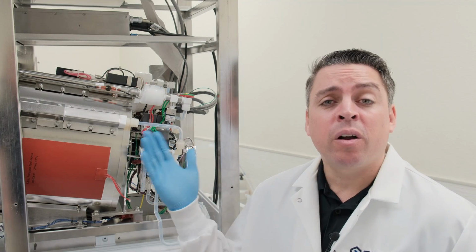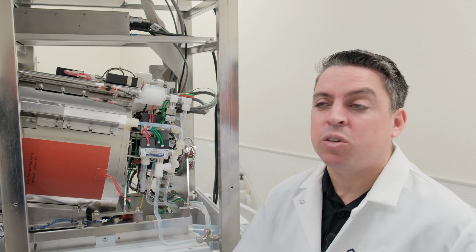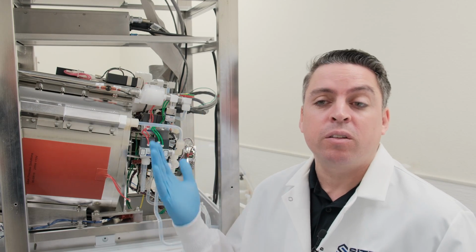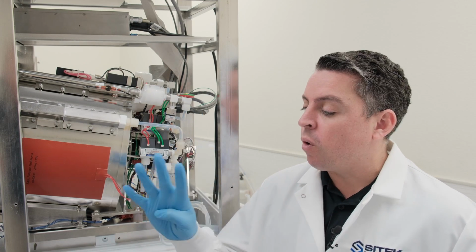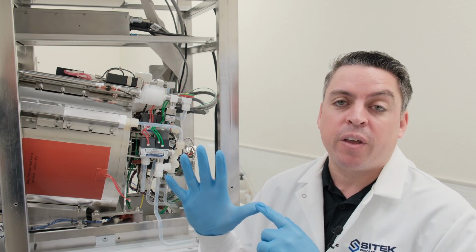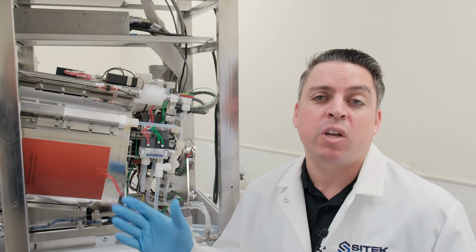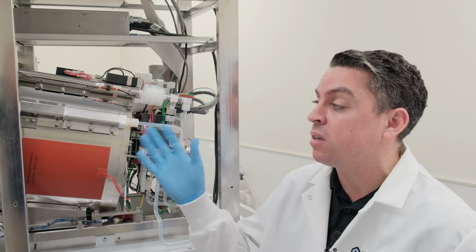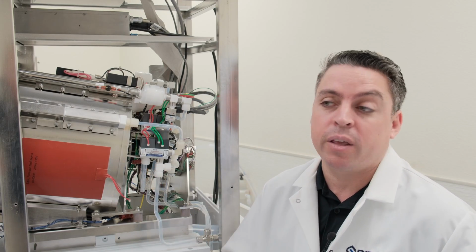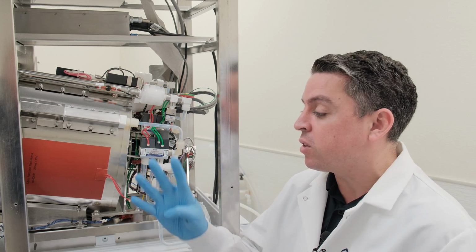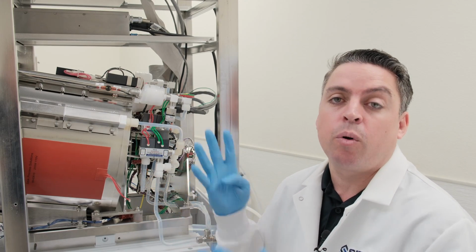Okay, and so here we are in front of an 8300S spin rinse dryer. What I want to do is show the various components that could have failed. We have mostly 4 components that could have failed and sort of a 5th if you count the cabling being disconnected. So you always want to make sure that you check that your cabling is all properly fastened on your system before going into too much troubleshooting. But of the 4 failures, 2 of them are common and 2 are more uncommon.